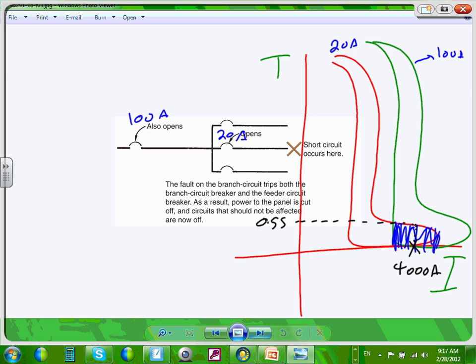Let's take another example. I have a short circuit here, let's say 3,000 amp. Can you guys see 3,000 amp? It will trip only, let's just say, at 0.4 second. Which one of them is going to trip right here? When that point went up, did it touch the green? Ask yourself, did it touch the green? No. So would the green trip then? No, it wouldn't trip. So that's what they call overcurrent protection coordination. So I am fully coordinated in this area.